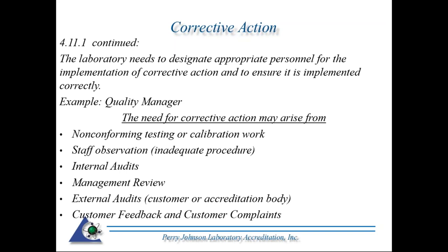And lastly, there's a note there. It specifies a need for corrective action may arise from, and this is not an all-encompassing list here, various elements which would require you to turn the keys and implement your corrective action procedure. Nonconforming testing or calibration work, i.e. using a piece of equipment that was out of specs, a technician not following procedure, using equipment that's exceeded its calibration interval.